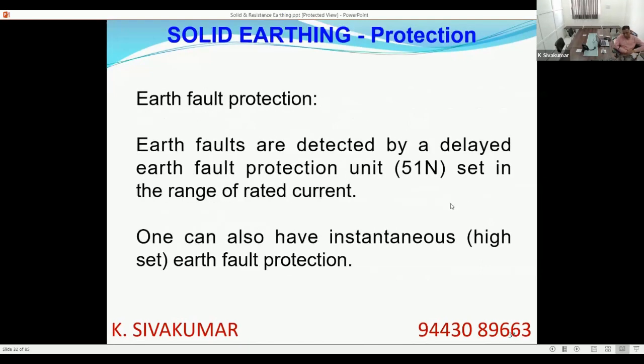So suppose we want to implement earth fault protection in a solidly grounded system. Generally, as I said, you definitely do not need a separate earth fault relay. The phase fault relays themselves will sense this high current and trip. But if you want a very sensitive protection, more than that offered by the conventional overcurrent relays or short circuit relays, you can always go for a 51N element, the delayed earth fault protection element, or you can go for an instantaneous 50N element, like we have seen in that scheme. Either 51N or 50N protection is possible because current is detectable.